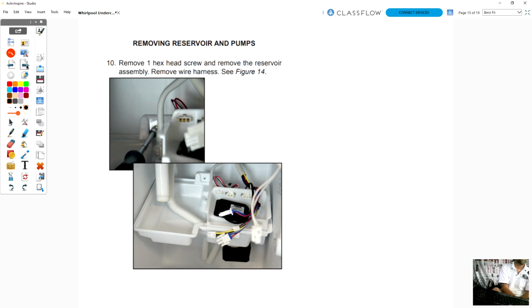So here is our recirculation reservoir, and there's a quick disconnect here. We have two connectors here. Actually, there's a third connector. One is for our recirculation pump. The other is for our drain pump, and third is the water level sensor, and I'll show you that in another picture. This compartment here is where the water comes in, and you can see this hose here. It's also here in the picture, and runs the water into this reservoir and fills the unit up. It's very hard to see, but right here is a hole, and that's an overflow hole. So if there's a little bit of remaining water left in it and it goes to fill up and the water level sensor doesn't shut it off, that water will overflow here, run down this hose here, and go out the drain. So that is the overflow.